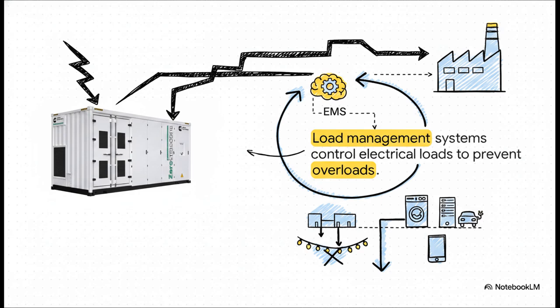What we're looking at here is a commercial battery energy storage system. To operate this safely and legally, it relies heavily on the code's exact definition of load management, which is a function performed by a listed EMS to control electrical loads. These smart systems can actually shed optional loads when power supply gets tight. That means you could potentially upgrade a facility's power capabilities without having to rip out and replace the entire physical electrical service. It's a real game changer.